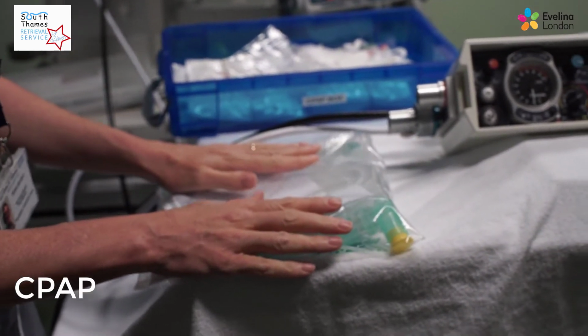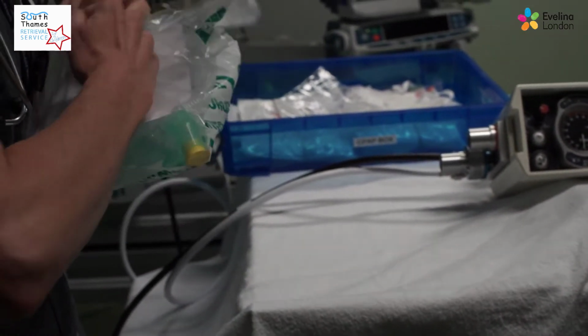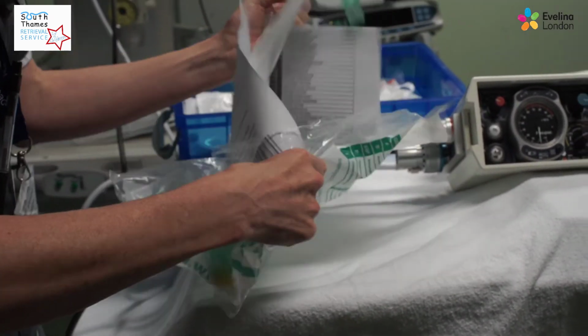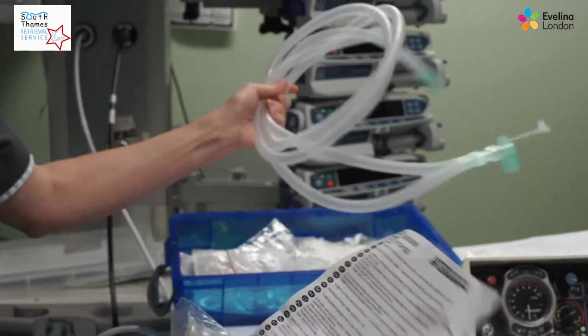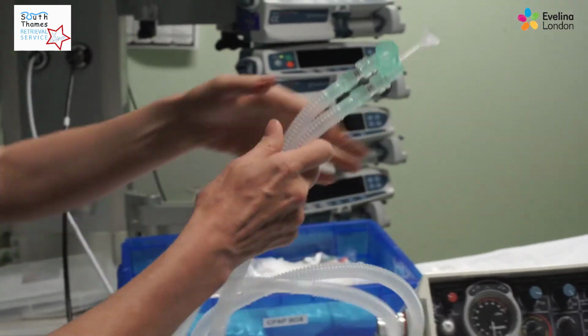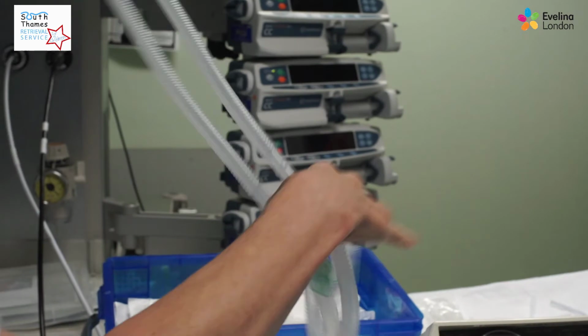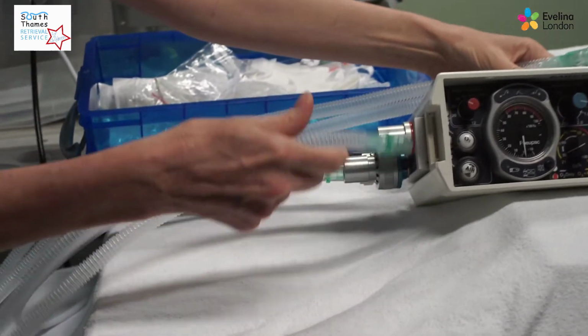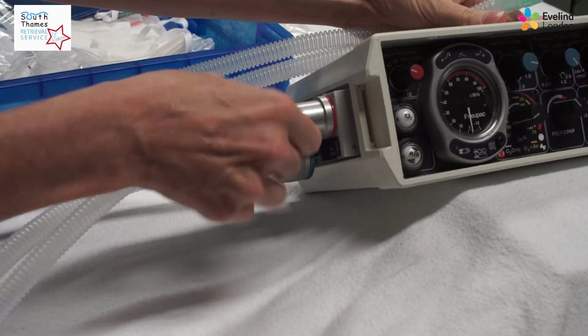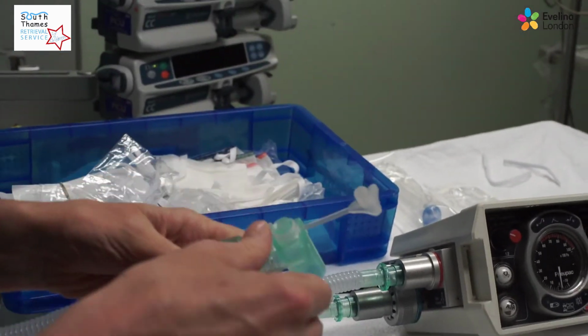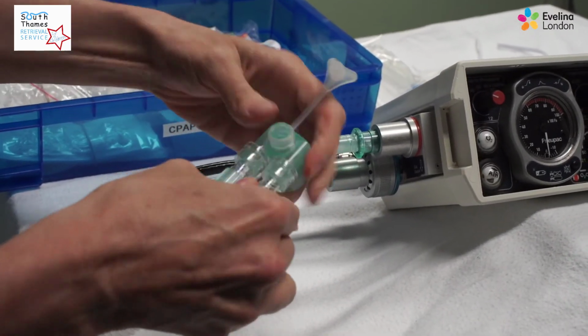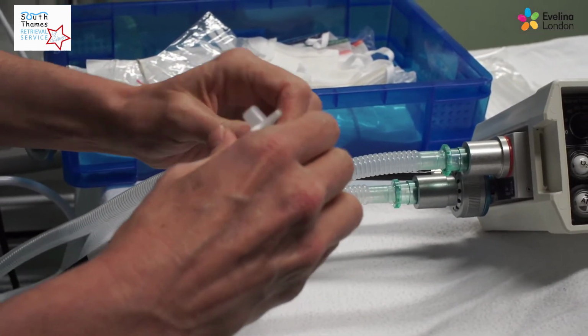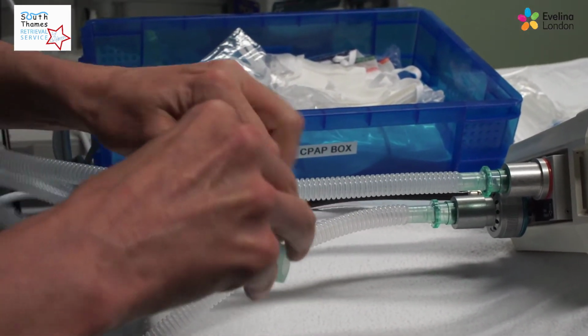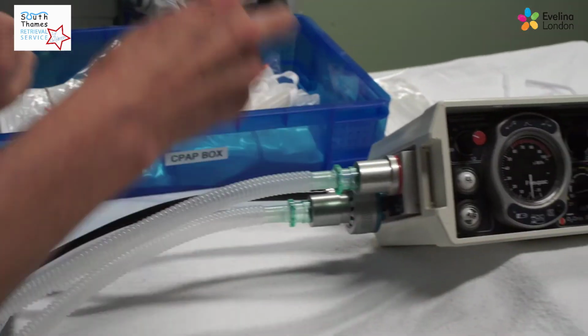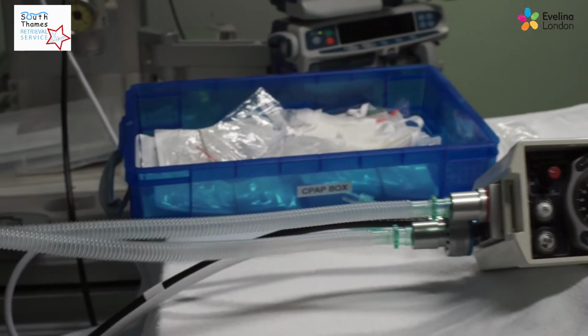CPAP is good for children 5 kilograms and under. It's a slightly different tubing from when we're using the Babypac ventilator as a ventilator on its own, and it has a single prong and much thinner tubing at the end. Again, it makes no difference which port the tubing is put into. Once we get to this bit, we disconnect the central hub, and we can keep that in case we need to convert the ventilator later.